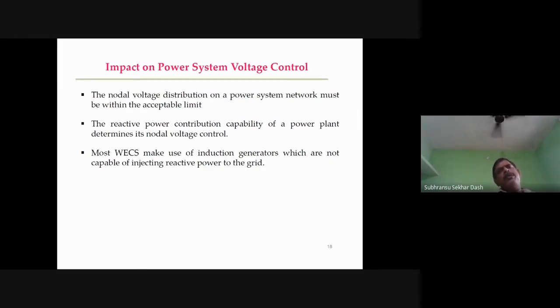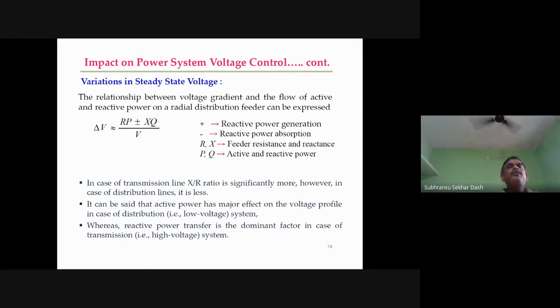You will see this in your HVDC sessions. What happened? You have an SVC or you have shunt reactors. Why do you use shunt reactors or SVC in the HVDC sessions? Because they inject reactive power to the grid. You know, reactive power is very much essential. If you don't get reactive power, you cannot maintain the voltage balance. To maintain the voltage balance, reactive power is required. You know that voltage fluctuation will be there, and there may be a voltage drop. So to maintain the voltage balance, you must inject reactive power to the grid.